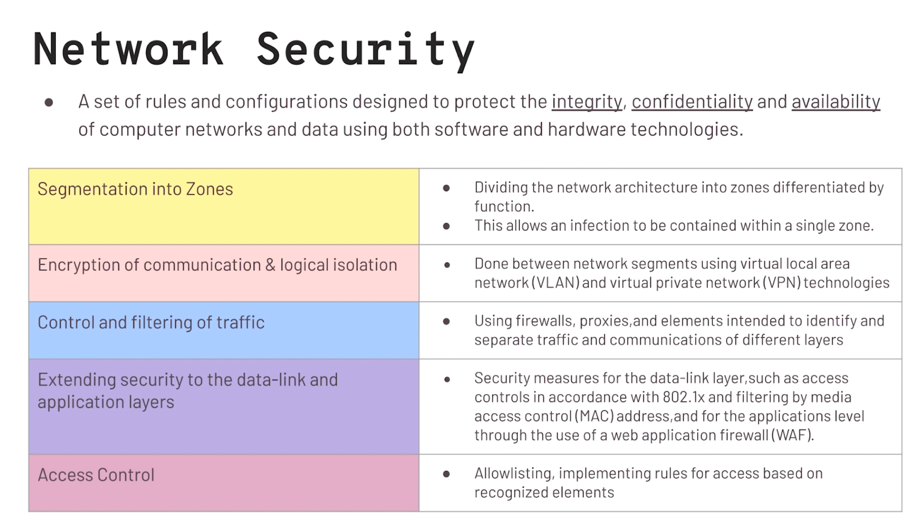For example, in the enterprise network, you have HTTP, you have FTP, you may have email, web servers. You don't want this traffic to go to your control network. At the same time, in your control network, you have Modbus, DNP3. You don't want this traffic going to the enterprise network. So firewalls can ensure that. And you have other ways, not just firewalls, but firewalls are primary elements of network security.